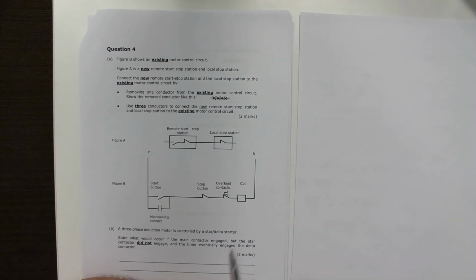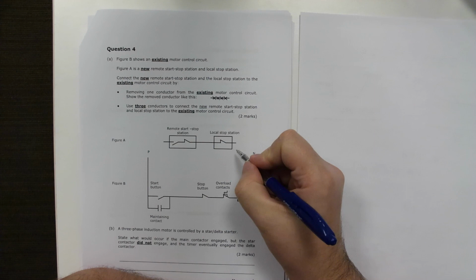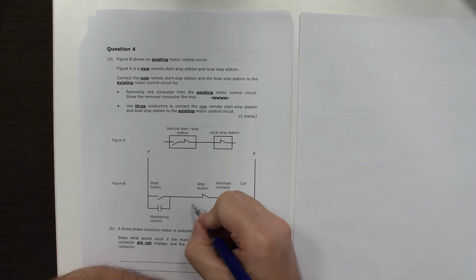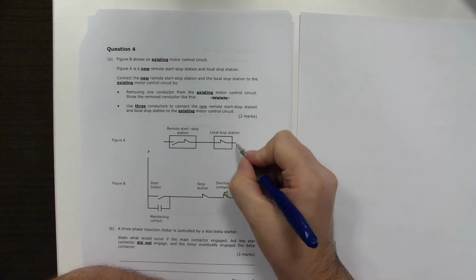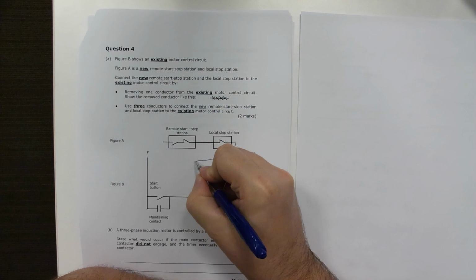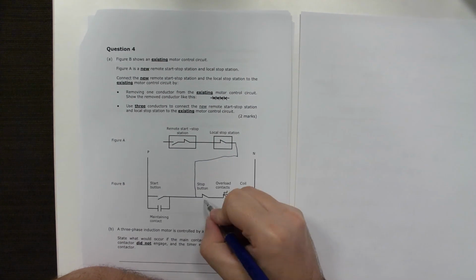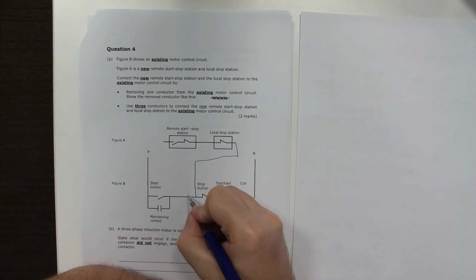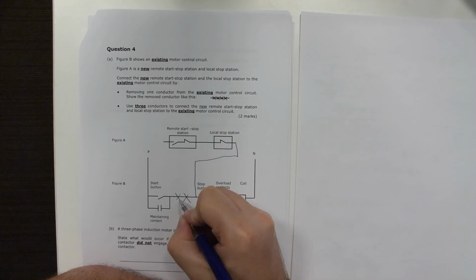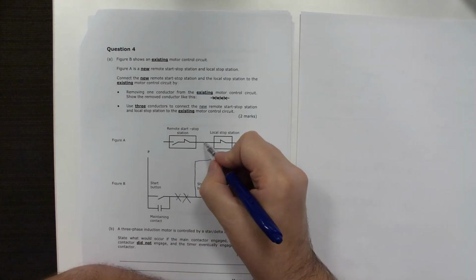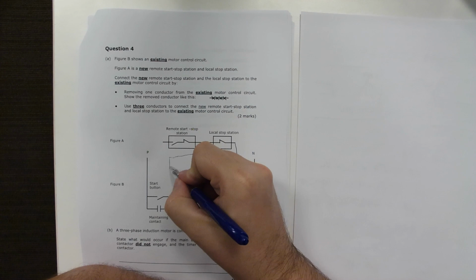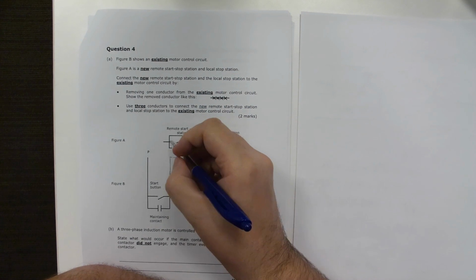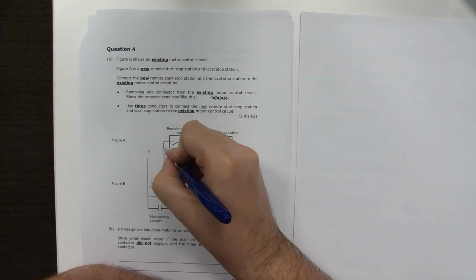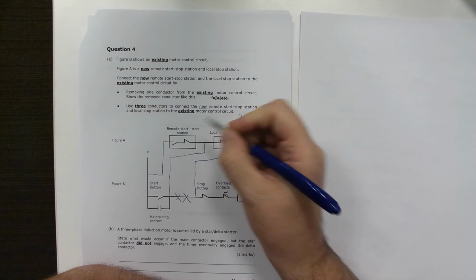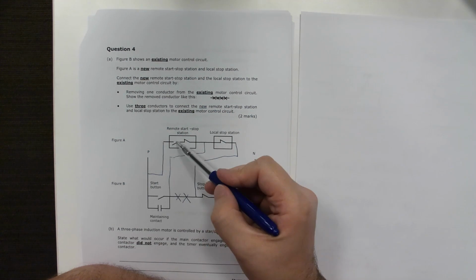So stops need to be put in series. So what we have to do is bring that one down. It goes to the start of that stop. Then we actually have to delete this wire here. And we need a new wire to come along and come down to there because the starts are done in parallel. That one can then go to there. So we've got that start.